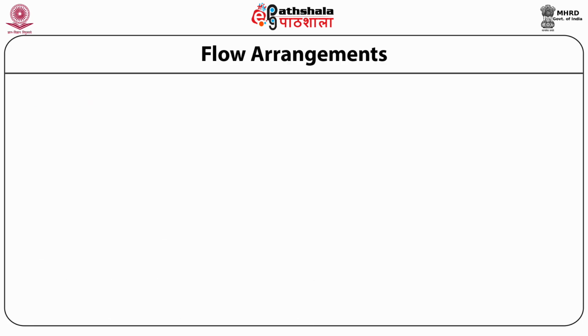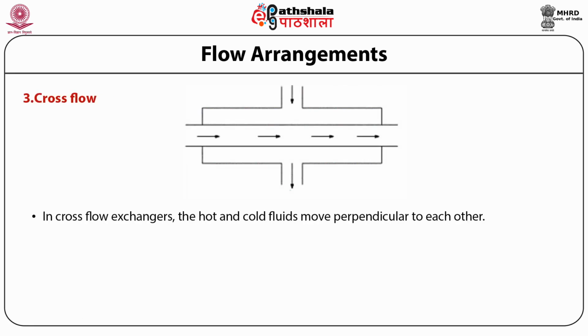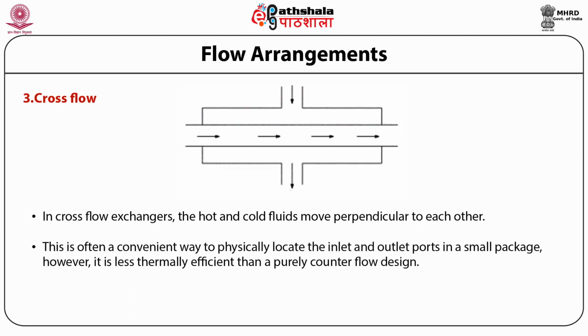Another pattern is cross flow. As shown in the diagram, in the case of cross flow, both fluids move perpendicular to each other. The hot fluid and the cold fluid move perpendicular to each other. This is often a convenient way to physically locate the inlet and outlet ports in a small package. However, it is less thermally efficient than a purely counterflow design.